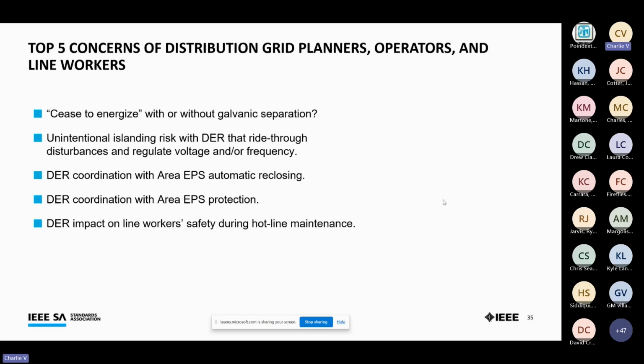So IEEE 1547 2018 has two very useful aspects. You can cease to energize, and the keyword is without tripping. If you trip, there's a return to service with that default 5 minute delay. But if you cease to energize, you can stay connected and synchronized as long as you're not transmitting real power, net power, back to the grid. There's some residual amount of reactive power you can transfer, but no real power. And that really improves grid reliability and grid performance in an era of increasing distributed resource penetration.